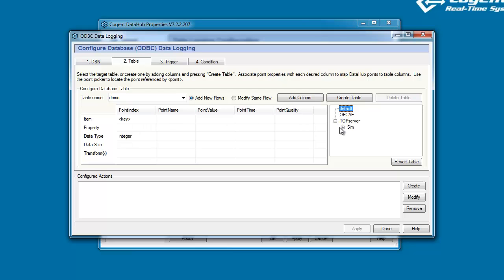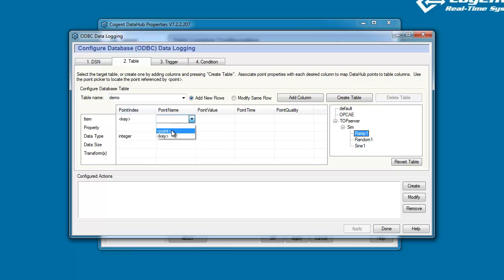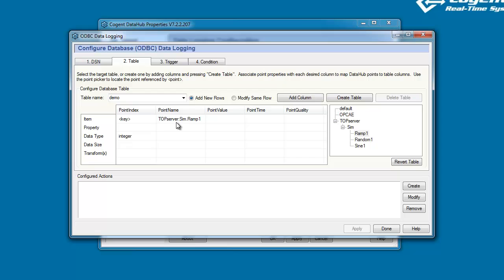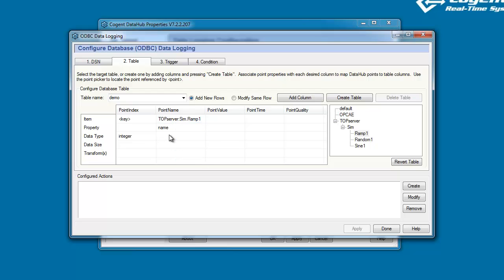Now I want to choose which data point I want to log in the database. For this example, I'm going to choose the ramp1 point. So, when defining the point name, I'm going to click to choose Point, and you'll see the Data Hub has filled in the point name for us, and the property I want to choose is the name, and its data type is a varchar or string. Now, depending on the data type you choose, the Data Hub will guess at an appropriate data size for you.